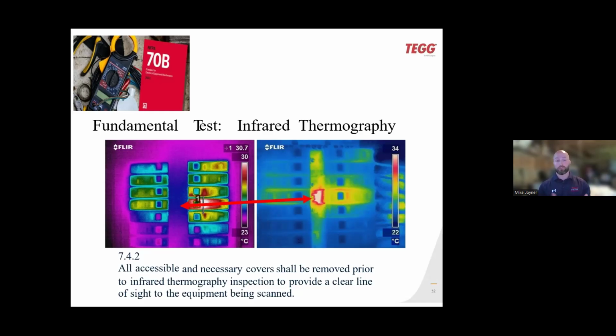The one on the left looks like a similar breaker, but that's hot in between the contact. We'd be able to figure out exactly and diagnose the issue, not just that it's hot. We'd put our meters on and dictate, hey, you'd have to replace this breaker - this breaker is actually failing. So it definitely takes somebody qualified, with the knowledge and background, to work as an infrared thermographer.